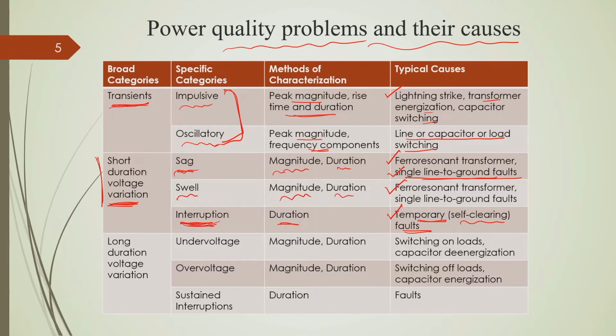Although these are short duration voltage variations, lasting from a few cycles up to 1 minute, their impact is very heavy. Those things we will discuss, and we have different mitigation approaches for them, which we will also discuss. Similarly, we have long duration voltage quality problems, which include under voltage, over voltage and sustained interruption. Under voltage is similar to voltage sag; it is a dip of the voltage which occurs for a period of more than 1 minute.